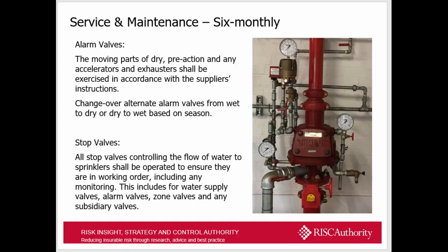Six-monthly requirements: alarm valves need to be overhauled, with moving parts exercised in accordance with the supplier's instructions. If you have any alternate valves — only present on existing systems as they are no longer permitted — they must be changed over every six months between warm and cold weather seasons, from dry to wet and vice versa. All stop valves controlling the flow of water to sprinklers shall be operated to ensure they are in working order, including all water supply valves, alarm valves, zone valves, and any other subsidiary valves on the system.